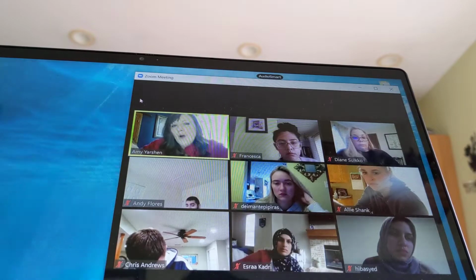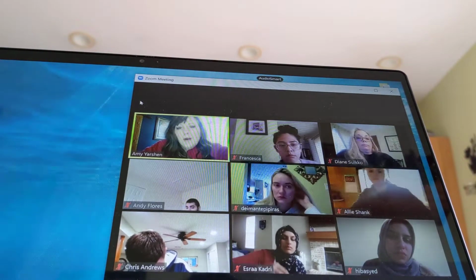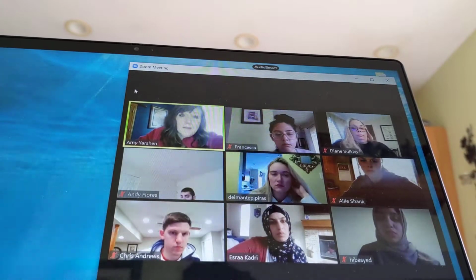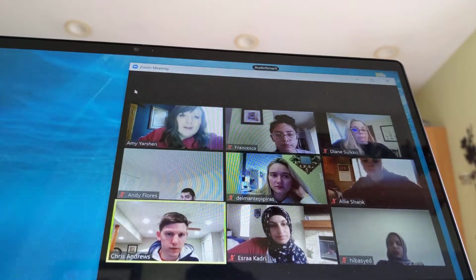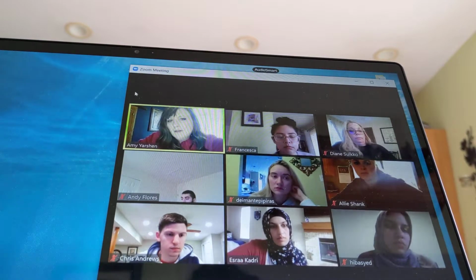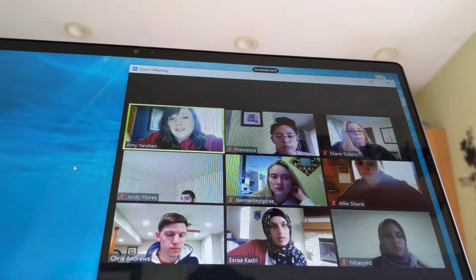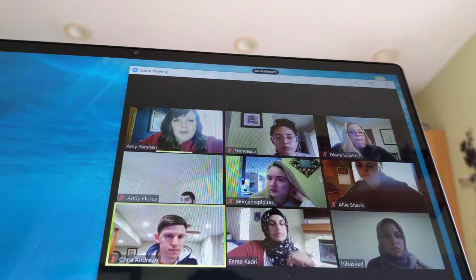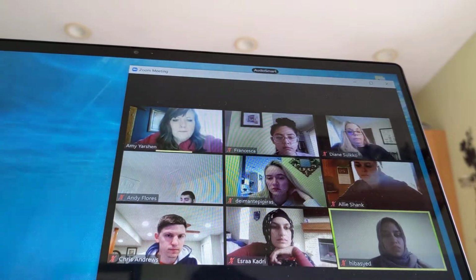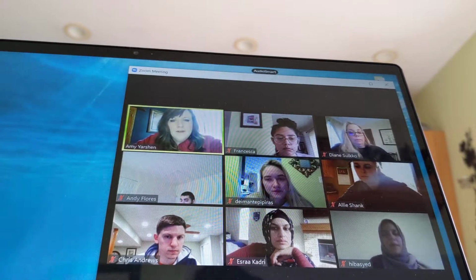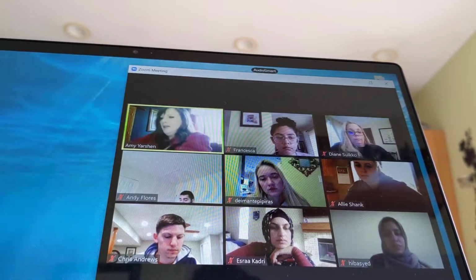But what do we do every day? What should be done? How often are bars done, guys? Bars assess linearity and resolution. How often is it done? Typically weekly, right? Weekly. Good. How about center of rotation? Some of you do it weekly, but at least it needs to be done monthly. Monthly. That's the minimum. That kind of thing. Does that help, Hiba? And more general, definitely more general.